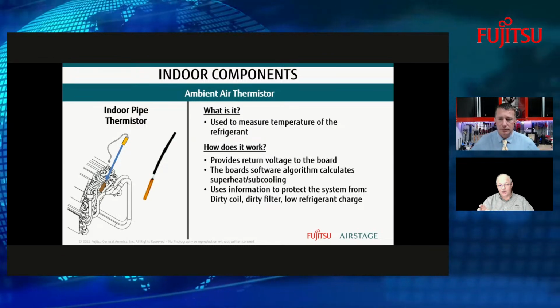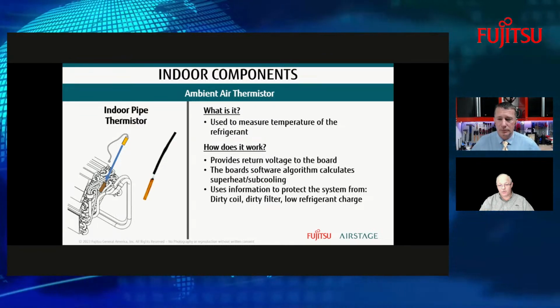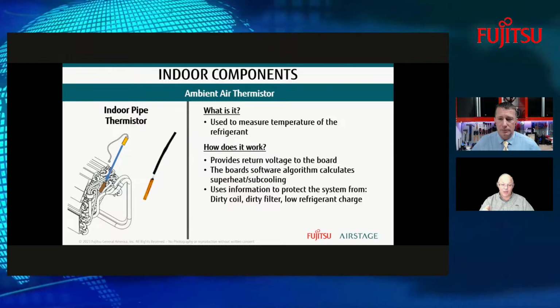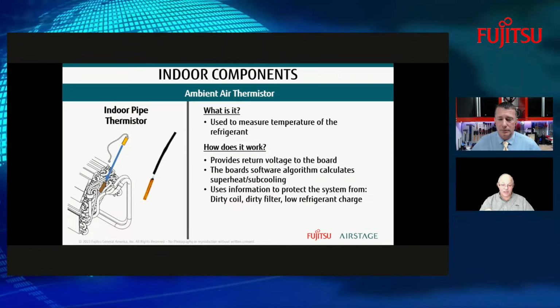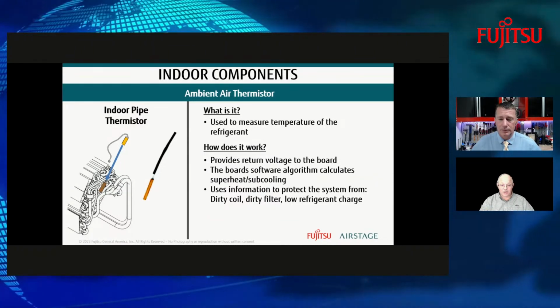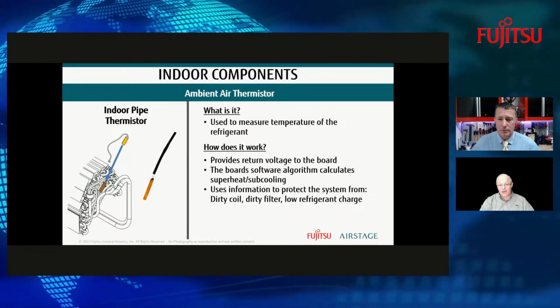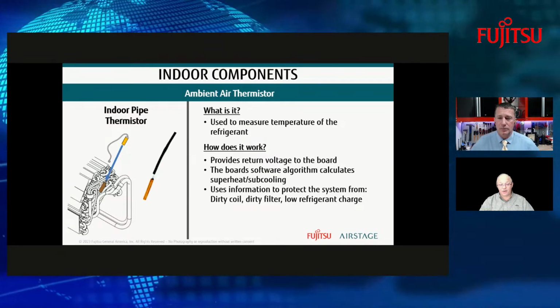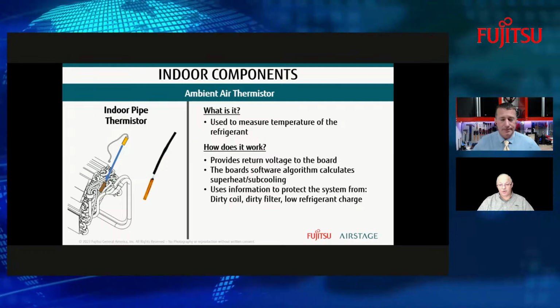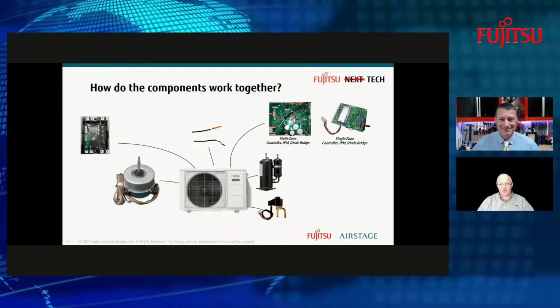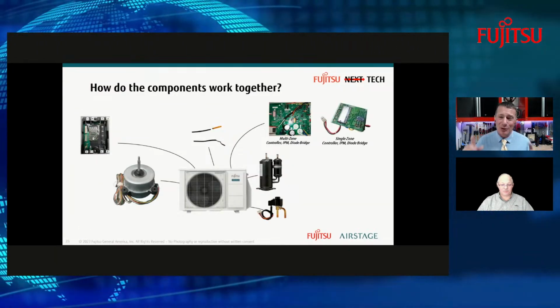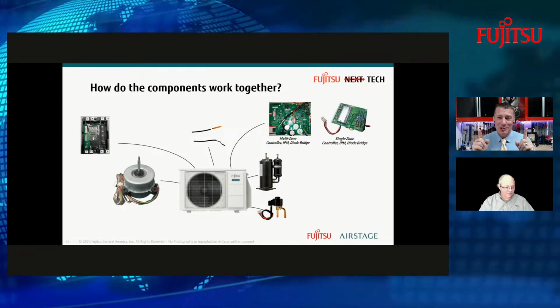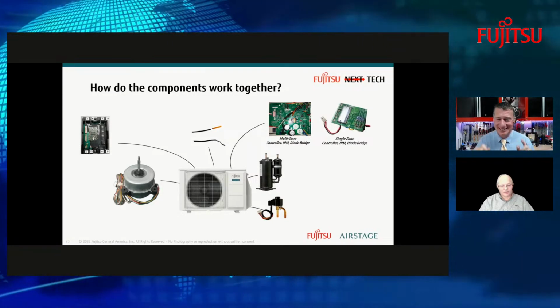So our system is looking to hit both a superheat and subcool target, which, by the way, you cannot set. That's all handled internally by the system, and the system is monitoring that continuously. So there are no charts for that, in case you wondered. Yeah, I have noticed because it gives a range. Said your superheat subcooling range would be in this.